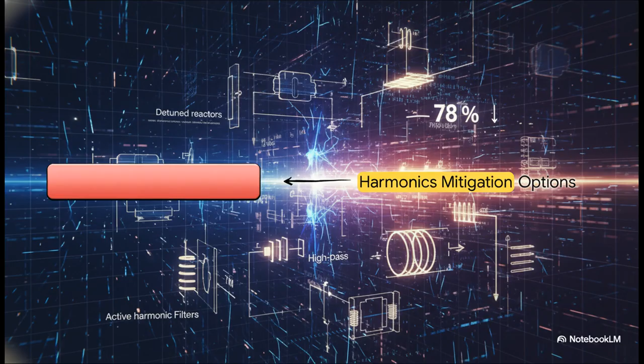As grid operators enforce strict new rules like the UK's G5/5, engineers deploy a whole suite of solutions to restore order. If the grid is too weak, we can try to increase system strength or change the point of connection entirely. But usually we rely on active harmonic filtering, detune reactors, or high-pass filters. In fact, a recent study showed that integrating detune reactors with high-pass filters can drop total voltage harmonic distortion by a staggering 78%. That's a huge win. Ultimately, winning this war requires a comprehensive defense strategy. It's a shared responsibility across the board.